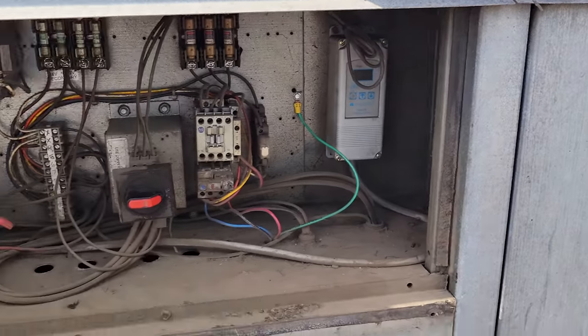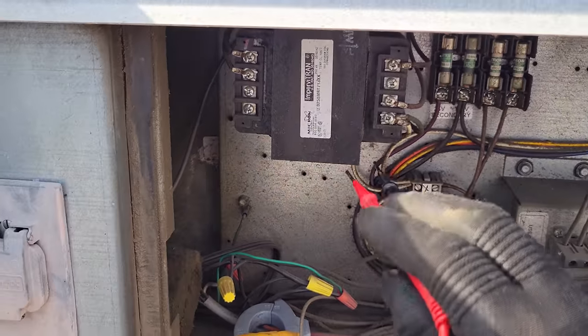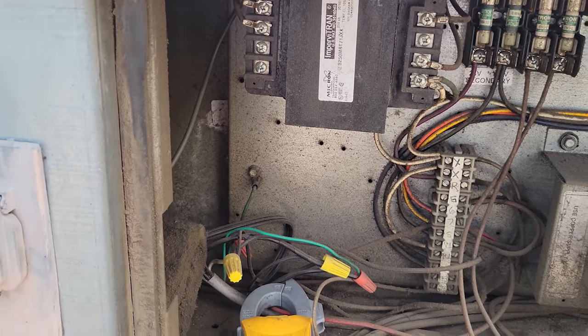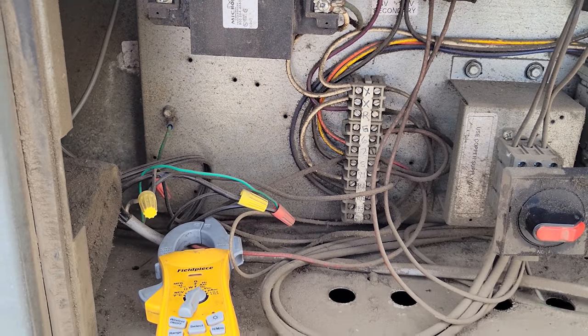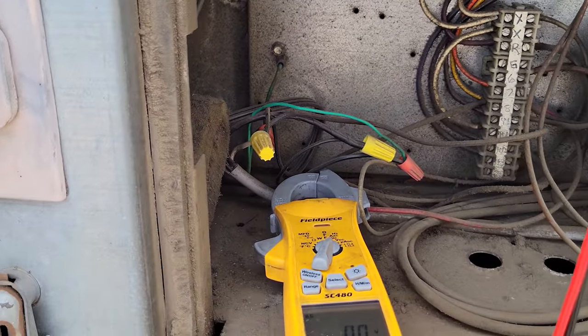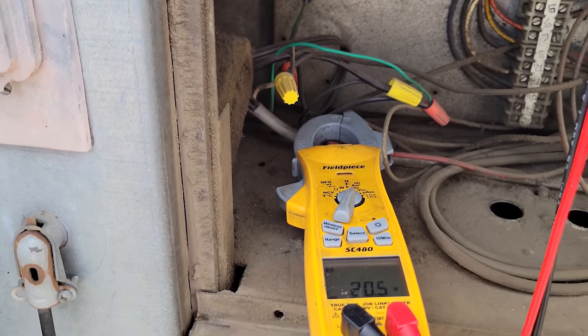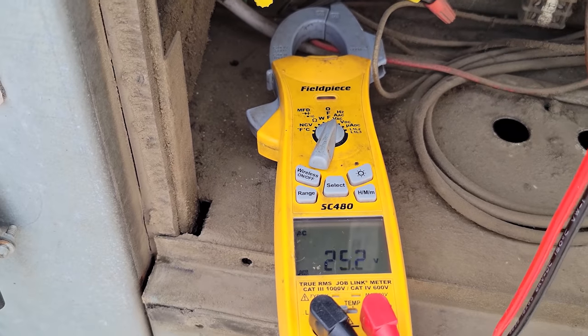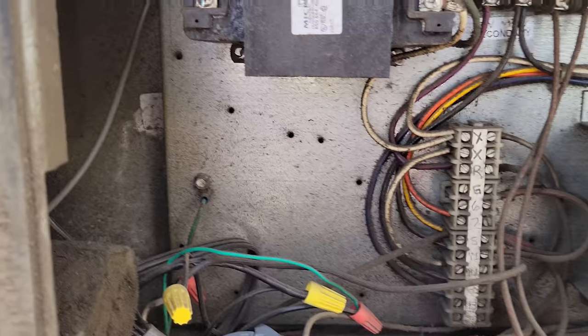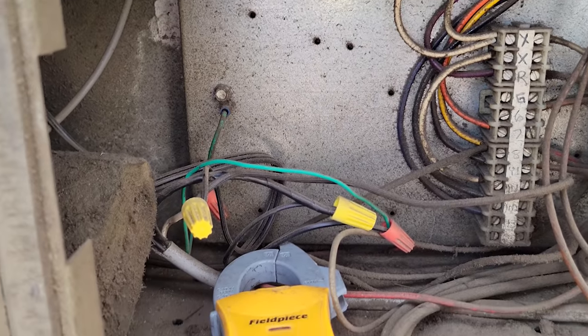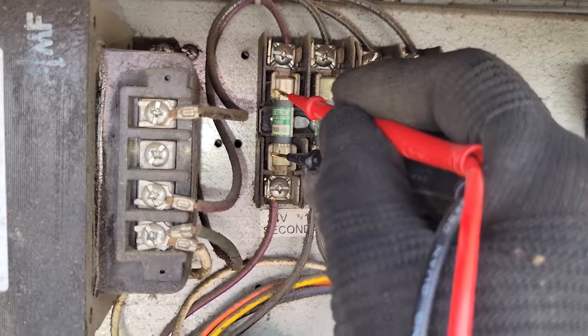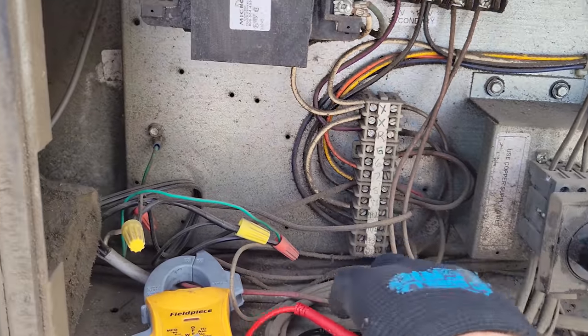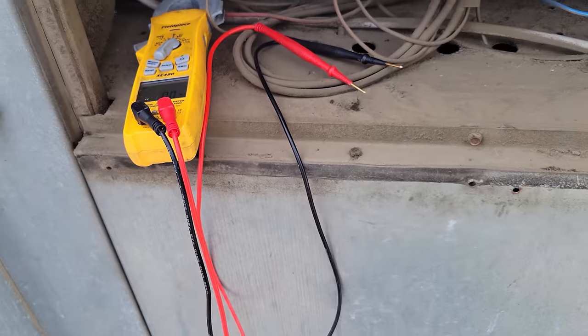This is their makeup air unit right here, and this is typically the source of control voltage for all the motor starters. This transformer, I believe right here, should give us 24 volts. And our motor starters are all 24 volts. But what's interesting is this is my 24 volt fuse and it's blown. 25 volts right there across that fuse. So we need to replace that fuse, but we don't know why it blew is the problem.